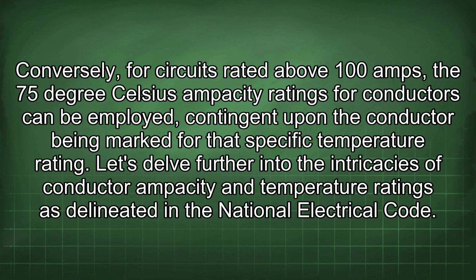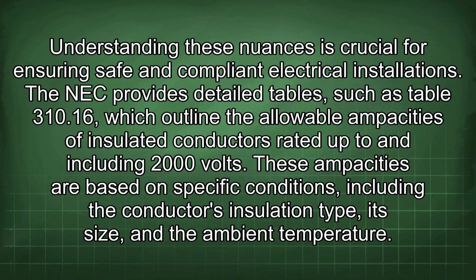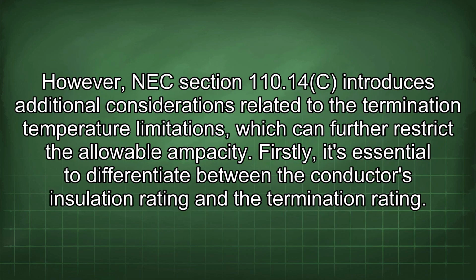Let's delve further into the intricacies of conductor ampacity and temperature ratings as delineated in the National Electrical Code. Understanding these nuances is crucial for ensuring safe and compliant electrical installations. The NEC provides detailed tables such as Table 310.16, which outline the allowable ampacities of insulated conductors rated up to and including 2000 volts. These ampacities are based on specific conditions, including the conductor's insulation type, its size, and the ambient temperature.